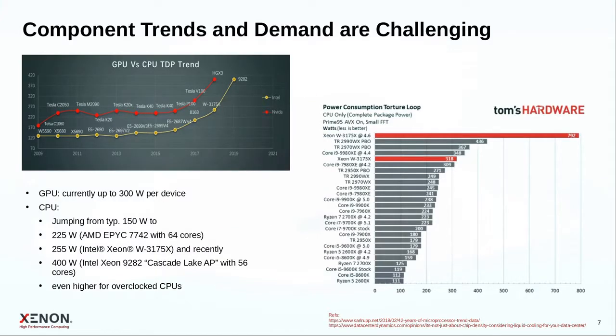That's underpinned by the actual technologies and components out there. On the graphs you see CPUs and GPUs with power consumption over time. We've been somewhere in the range of 120-150 watts on the CPU side, and right now in the latest generation Cascade Lake AP CPUs, we're going up to 400 watts per package. Similarly on the GPUs, we've traditionally been somewhere in the order of up to 250 watts, because that was essentially what was feasible based on power availability in server systems. We've gone up to 300 watts with the SXM2 V100 modules, and that scales up as we go to larger systems.